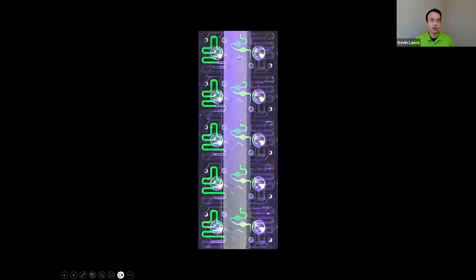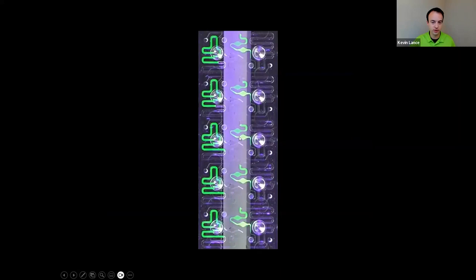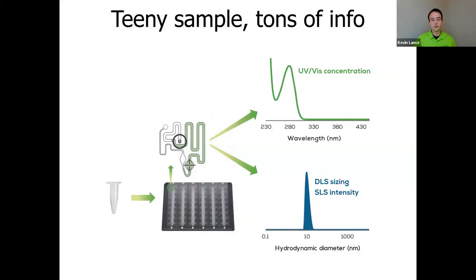Once inside Stunner, the sample is pumped into those path lengths — those microcuvettes with fixed path lengths — and that's where your UV-Vis and DLS reads are done. Because those path lengths are fixed, that allows Stunner to get incredibly accurate and precise readings on your UV-Vis information, and we can use that to calculate how much protein and DNA is present and understand the empty-full ratio. DLS gives us size and aggregation information, as well as the underlying data for capsid titer. The raw data from an AAV sample shows a UV-Vis absorbance read that typically peaks between 280 and 260 nm, plus a DLS read.